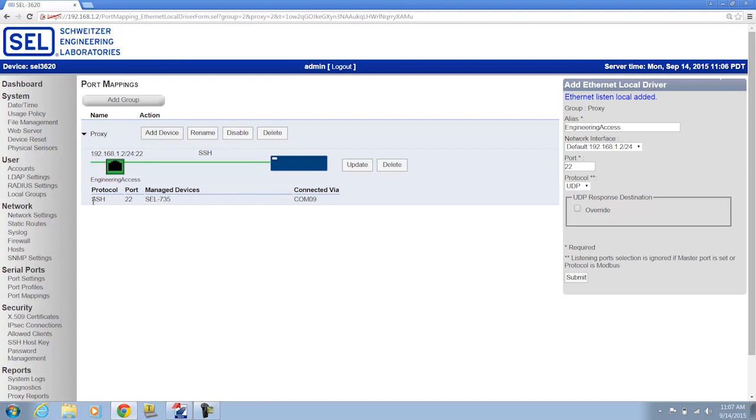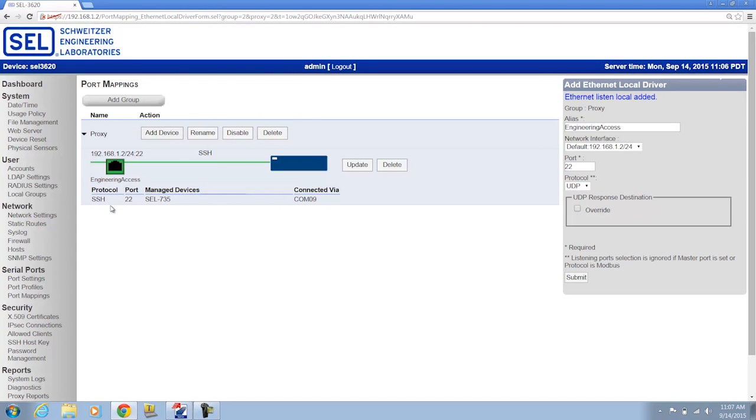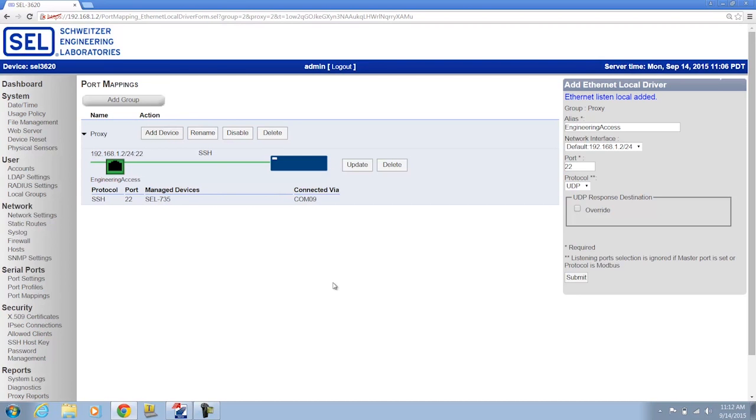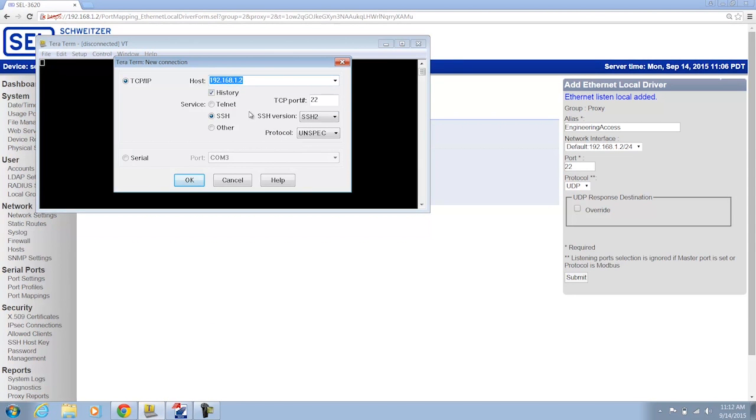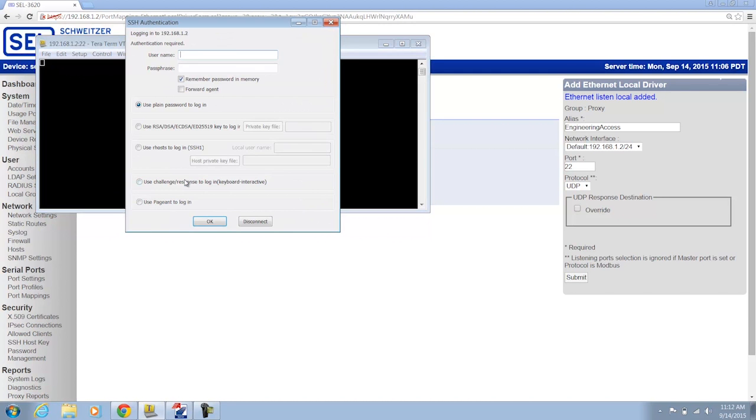Now, how I as an engineer would access this relay is using the SSH protocol via port 22. So that's what this information means when I go to the port mappings page on the SEL3620. Now what I'm going to do is I'm going to use something like Putty, or I could use a terminal software that's built into AcSELerator QuickSet. I'm going to use Tera Term in order to access this SSH interface that I just created on my 3620. So I'm going to open up Tera Term. I'm going to make sure I have the correct IP address, the protocol, and the port number. And I'm going to go ahead and access the interface, the 3620.